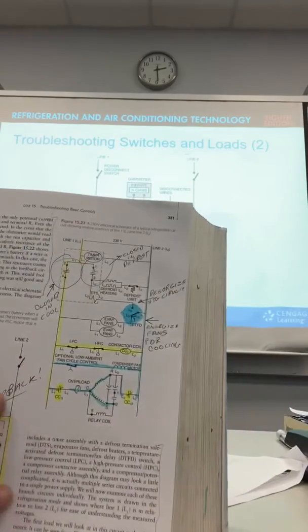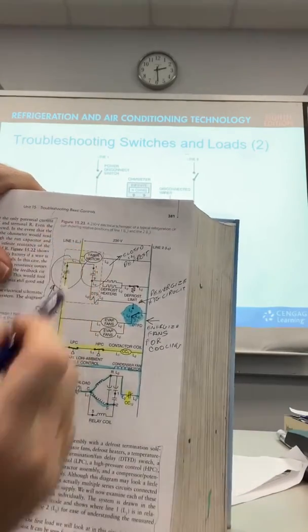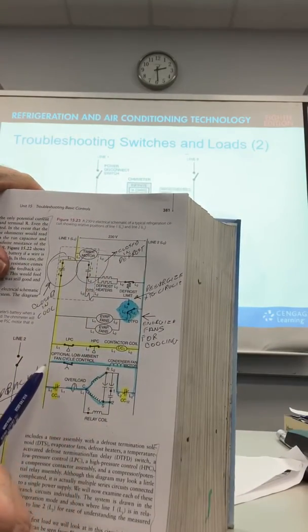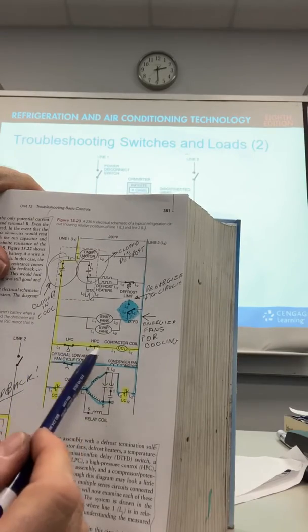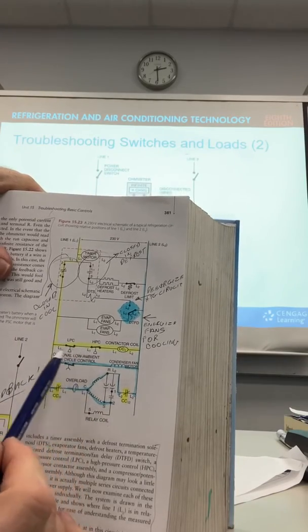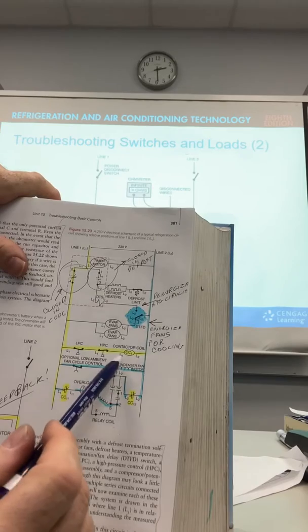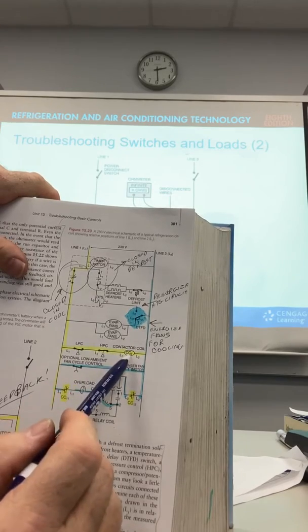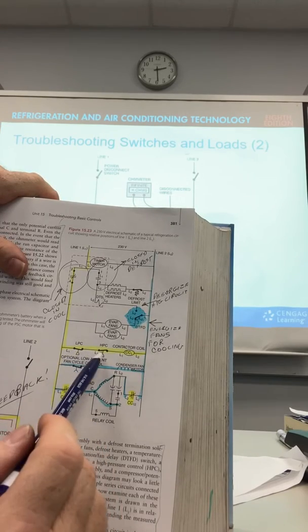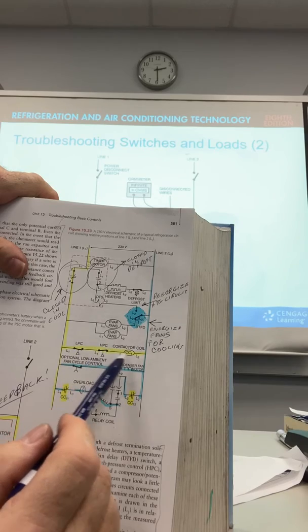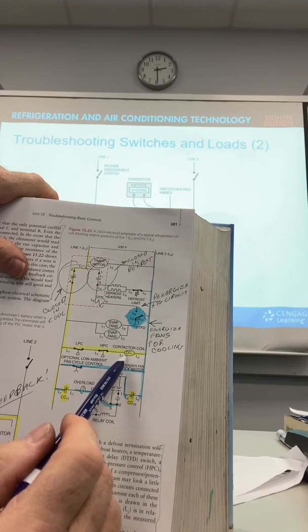I'll go over it with you real quick. They're just showing you in a refrigerator the set of switches in series going to the load. Here's the contactor coil. If the low pressure control or high pressure control opens, the contactor turns off.